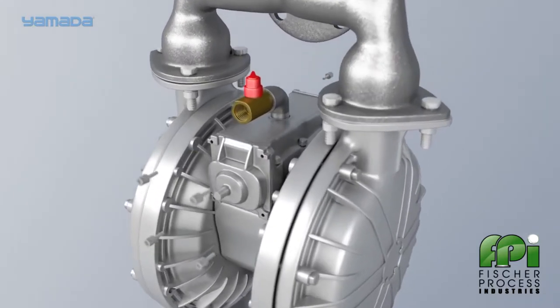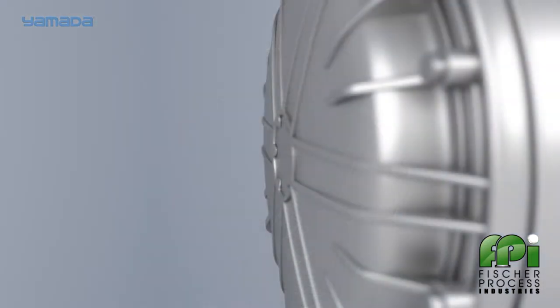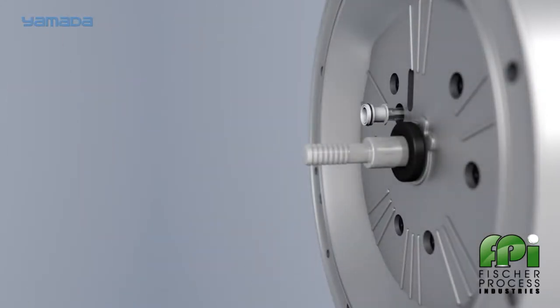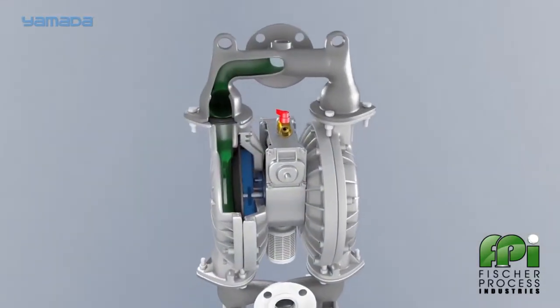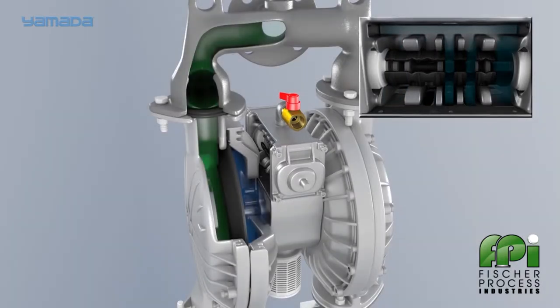What separates Yamada from the rest of the pack is our air valve technology. Yamada uses a completely non-lubricated main air valve and independent pilot mechanisms to control the air logic. As compressed air enters the pump, it is directed via the main air valve to one side or the other depending upon the starting position of the c-spool.